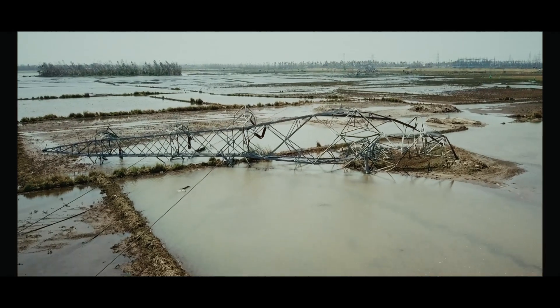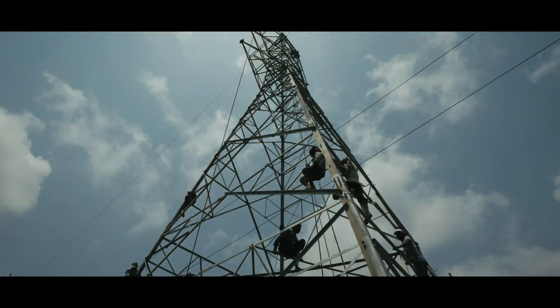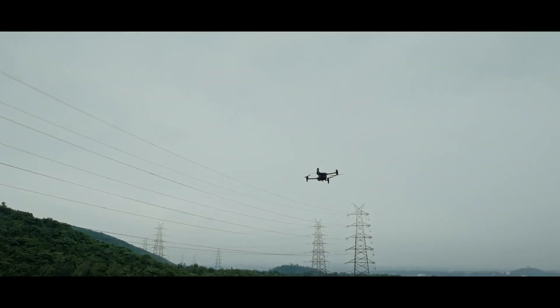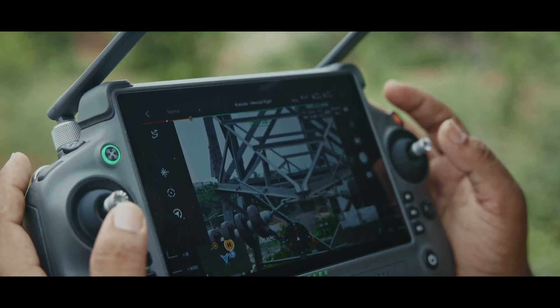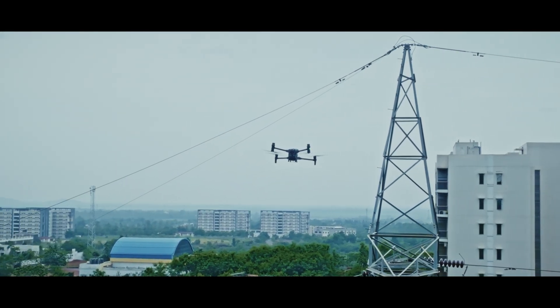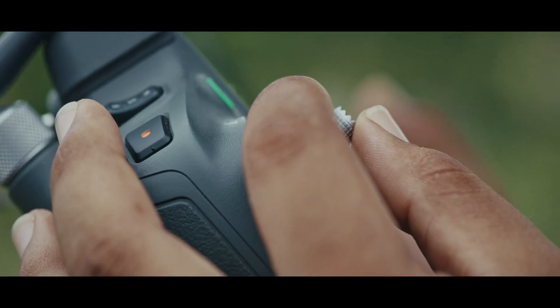Odisha's power infrastructure faces frequent damage from natural disasters, making it crucial to strengthen the EHV network. Drone-based surveys and maintenance, especially for inaccessible areas, are now strategically used for patrolling and preventive maintenance. This includes 400 kV, critical 220 kV, and selected vulnerable 132 kV networks, while mobile app-based inspections cover the rest.